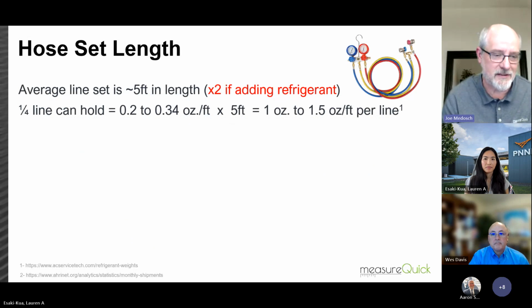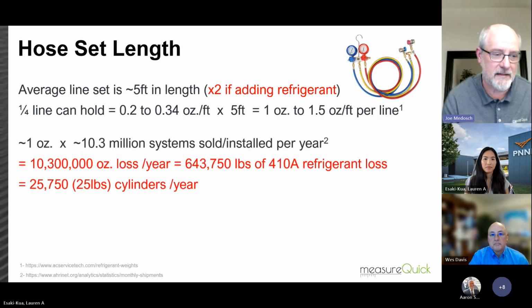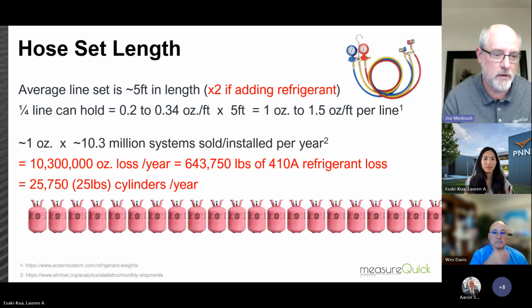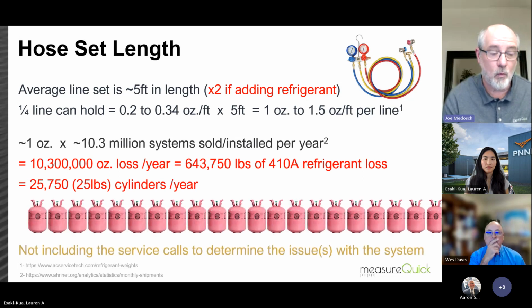So if I have an average line set that's 5 feet, and in that line set is about 0.2 ounce per foot, that adds up to about 1 ounce in the line set. And if you're doing an exchange, like actually adding refrigerant, you actually have 2 line sets - one that's measuring and also adding it.